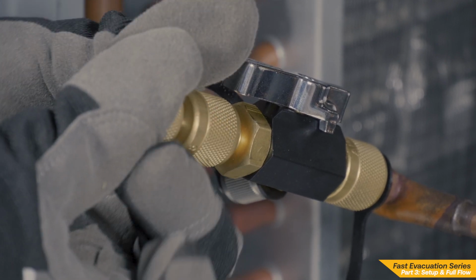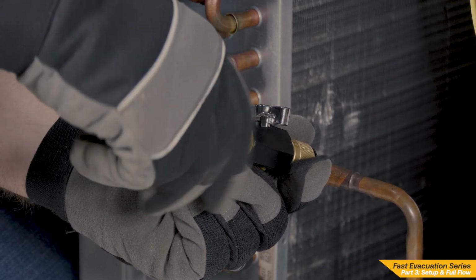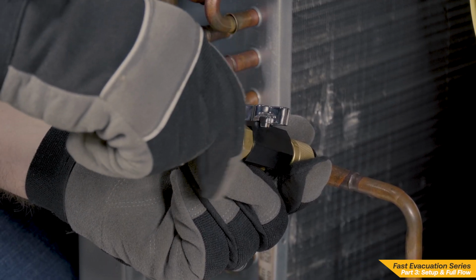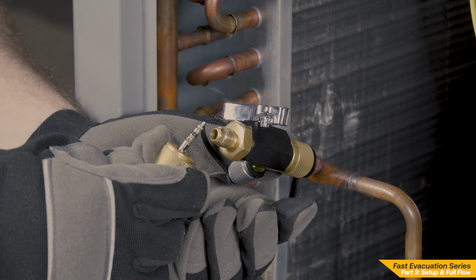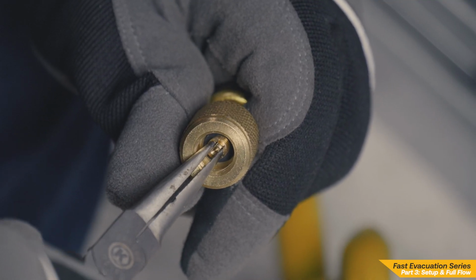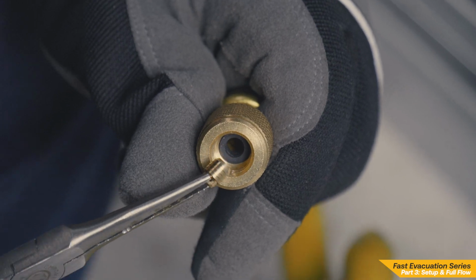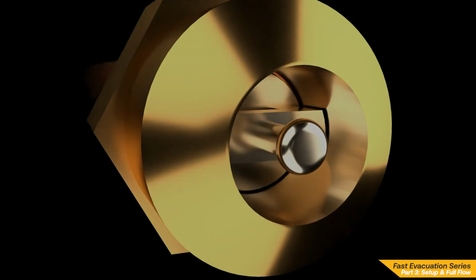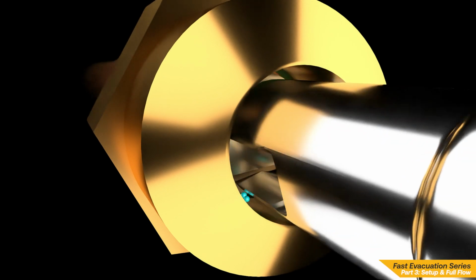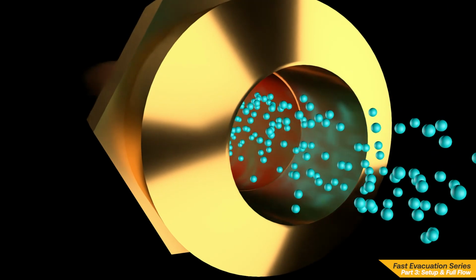To achieve full flow, start by removing all controllable restrictions, including valve cores in system access ports, and any core depressors from your vacuum hoses. These restrictions act as plugs and can reduce flow to as little as 0.2 CFM. Once they are removed, you will allow unrestricted flow of molecules.